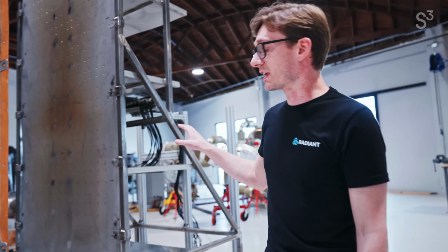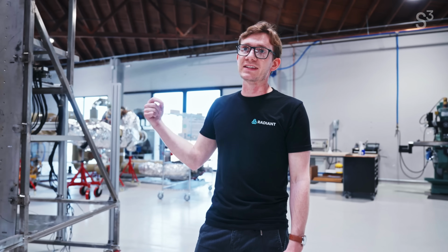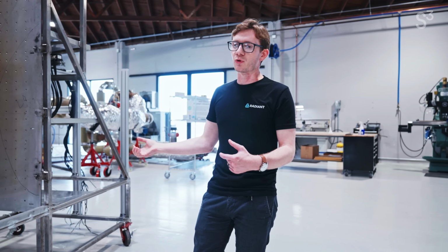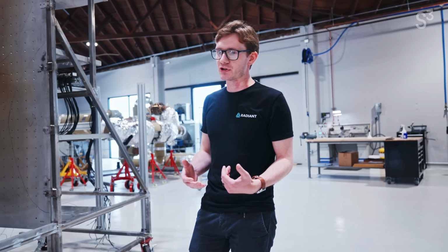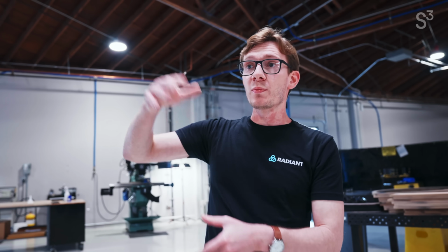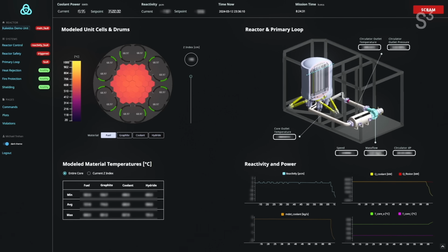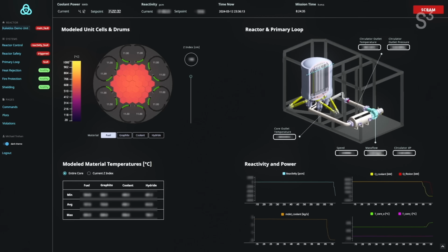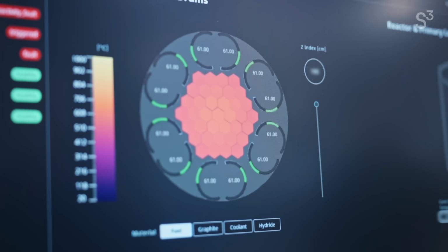This enables us to get the science to prove exactly how much heat we'll be able to reject passively from the pressure vessel. If there's any kind of accident scenario with the reactor, that airspace opens and then cold air comes in, picks up some heat and rejects it to the environment. The fuel stays cold, the pressure vessel stays cold, and the reactor safely shuts down.